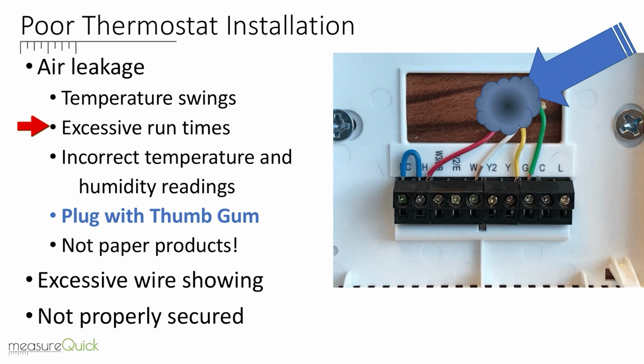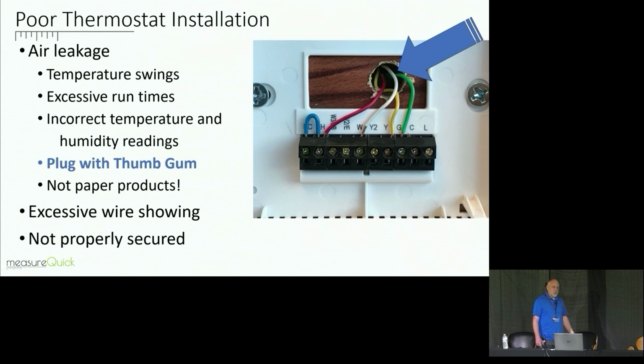Now, you think about these kinds of things, and a lot of people don't realize that that's going to cause excessive run times. In fact, a lot of you guys have probably come home from work, walked in your house, and said, dang, it's cold in here today, right? Because it's a 95-degree day outside. And what you don't realize is your thermostat's registering 78, so your unit's running continuously, but your air temperature is probably down to 74 or 76 degrees because you're getting air from an unconditioned space.